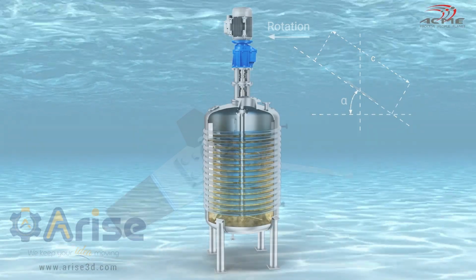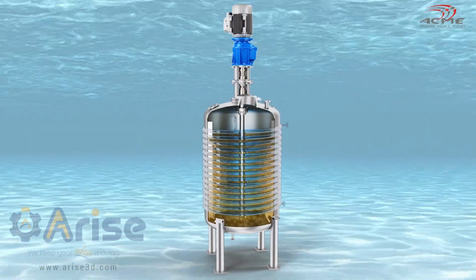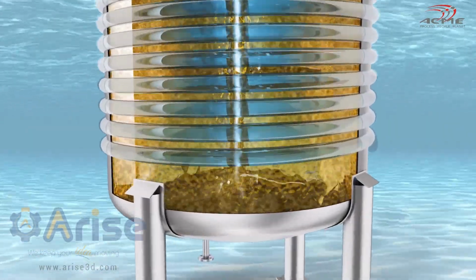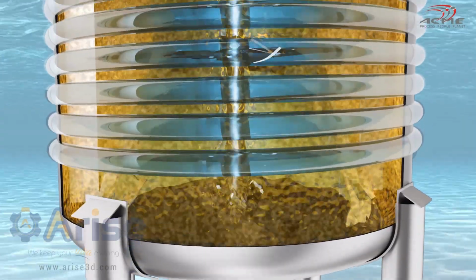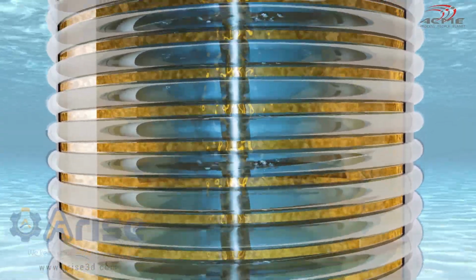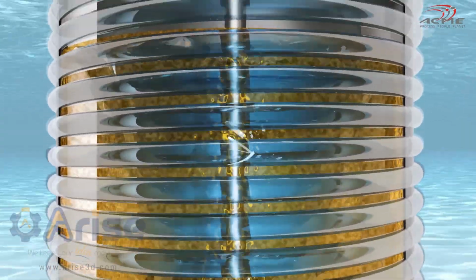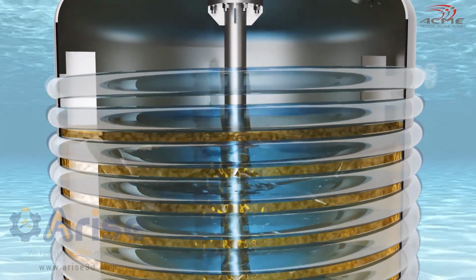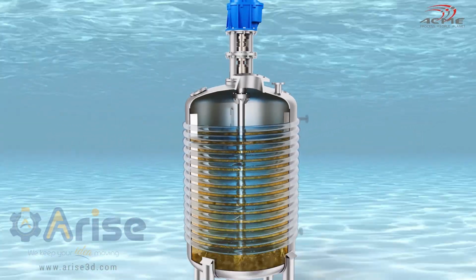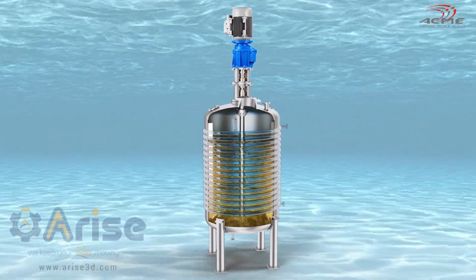consumption. For low to medium viscosity industrial applications, a narrow blade hydrofoil impeller provides superior overall heat transfer performance compared to a pitched blade turbine due to higher axial flow, enhanced circulation, and more uniform mixing across the vessel.